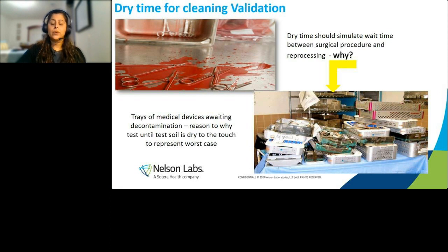Now, dry time validations. Back in the day, when I first started my job at Nelson Labs, we would have a wet towel with water, and we would place it on the devices for 30 minutes so they would keep moist, because those were the actual procedures that were happening in the hospital. So to mimic that, we did that. Over time, things have evolved and changed when it comes to these validations, and we are trying to mimic what is happening in the actual facility now, right? You want to make sure that you are challenging the cleaning as much as you can. So it has come to the point where all the validations are now performed with the test soil left to dry at room temperature.